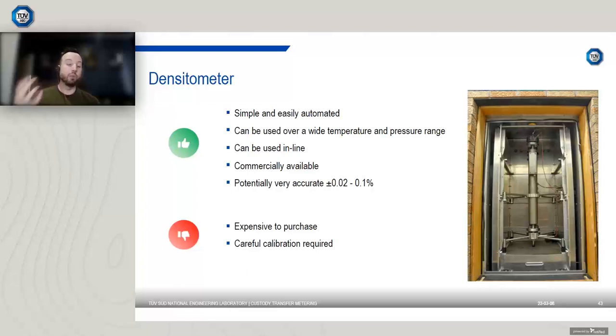The downsides are they can be expensive to purchase, and in order to meet that kind of uncertainty, careful calibration is required. The image here is actually a densitometer being calibrated at NEL. We have a liquid densitometer facility where we calibrate densitometers over a wide range of temperatures and pressures. To meet these uncertainty targets, you really do need to calibrate the device.